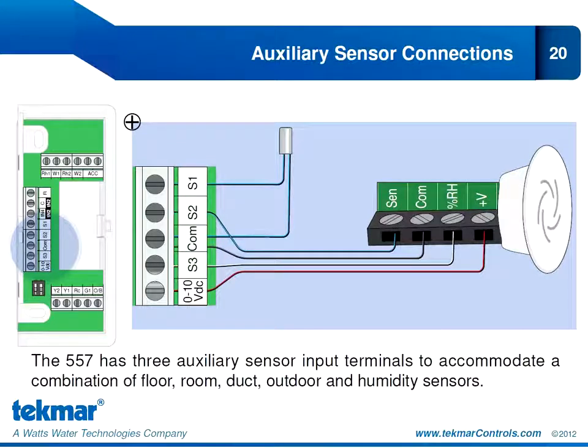The 557 has 3 auxiliary sensor connections, and they can be configured for any combination of sensors, including a floor sensor, room sensor, duct outdoor sensor, and even a humidity sensor. As you know, the 557 does have a built-in humidity sensor, but if we want to take into account a humidity measurement in another area of the building, we can do so by connecting the external humidity and temperature sensor 086. Now the 557 will use both humidity measurements and average them.